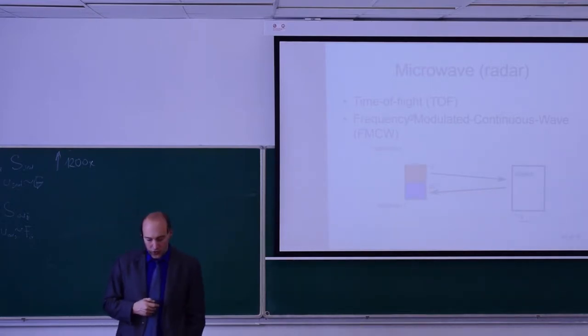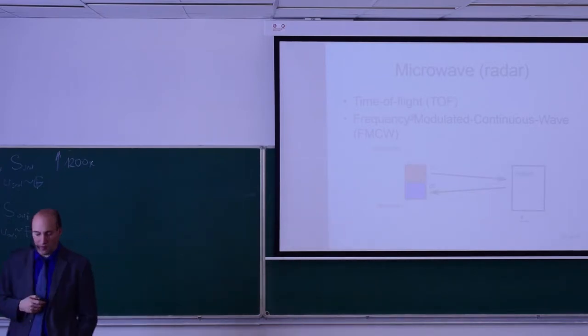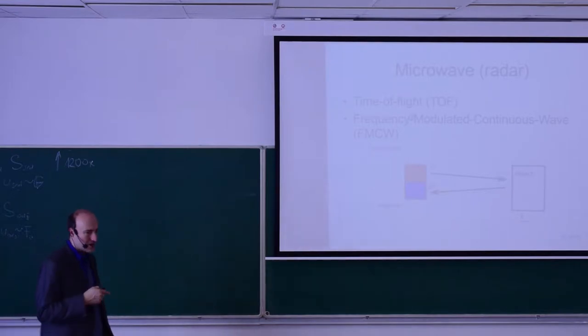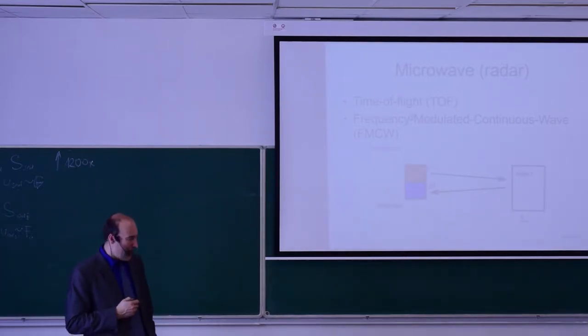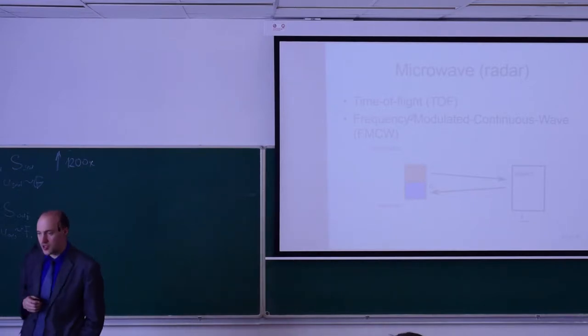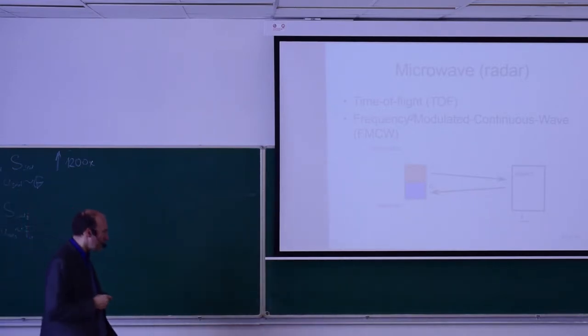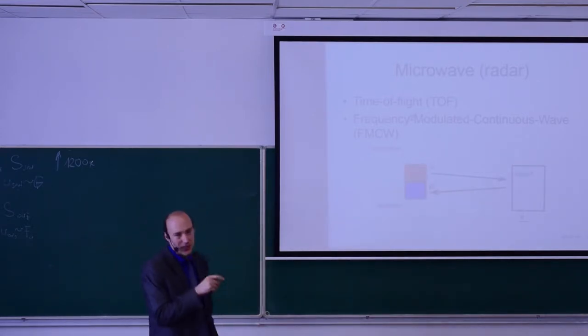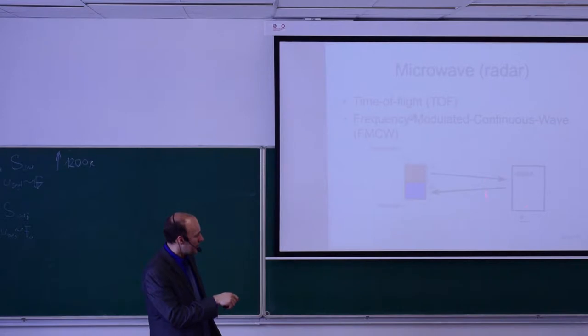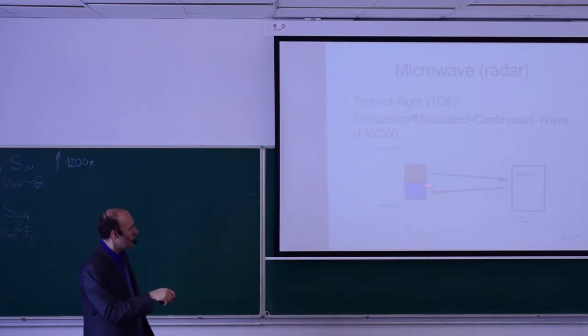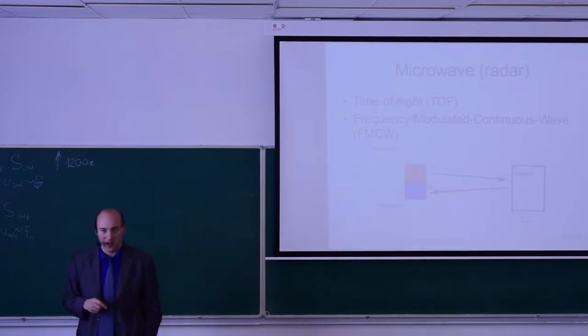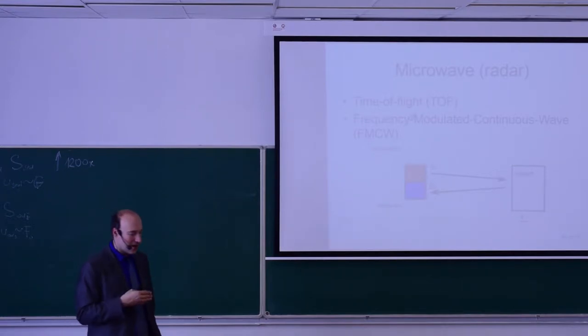There are basically two principles used. One is the measurement based on the time of flight, used especially for longer distances. The second principle is called frequency modulated continuous wave, used for shorter distances. In both cases you have a transmitter sending either a pulse or a continuous wave, and an object reflecting that wave. The object needs to reflect the radio signal well, and you need to select a suitable frequency range where the echo would be best.